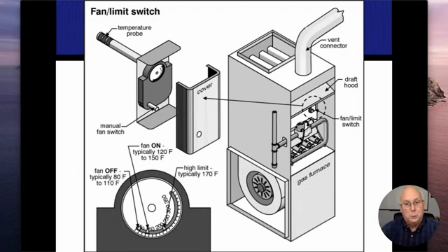All right. So when the furnace would kick on, the burners would ignite and they would start heating up the heat exchanger, and the fan wouldn't kick on right away because the air around the heat exchanger is still cold. And we don't want to circulate cold air. We want to wait till it gets warm. So that would wait till somewhere around 140 degrees. All right. At 140 degrees, this probe would flip a switch and say, okay, blower fan, you get turned on. All right. But again, let's say that blower fan was broken and it didn't operate. Then it would keep getting hotter and hotter and hotter until it reached somewhere around 170, 180 degrees. At that point in time, it's too hot, and that would actually turn the fire off and shut down the whole furnace and let everything cool back down again so that it didn't burn the house down, or start on fire itself.